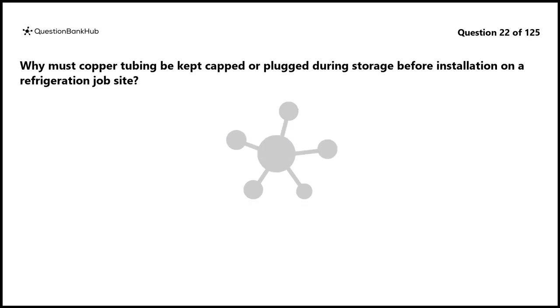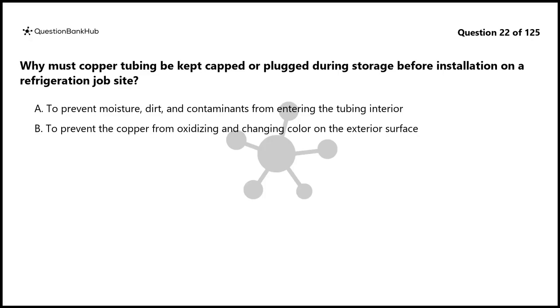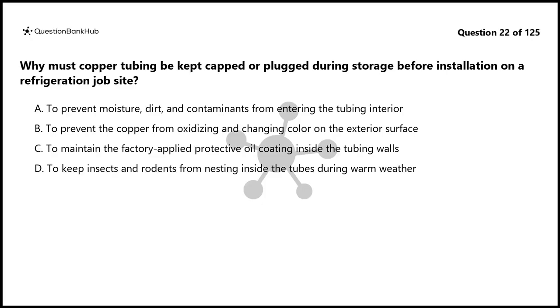Question 22. Why must copper tubing be kept capped or plugged during storage before installation on a refrigeration job site? A. To prevent moisture, dirt, and contaminants from entering the tubing interior. B. To prevent the copper from oxidizing and changing color on the exterior surface. C. To maintain the factory-applied protective oil coating inside the tubing walls. D. To keep insects and rodents from nesting inside the tubes during warm weather. The correct answer is A.